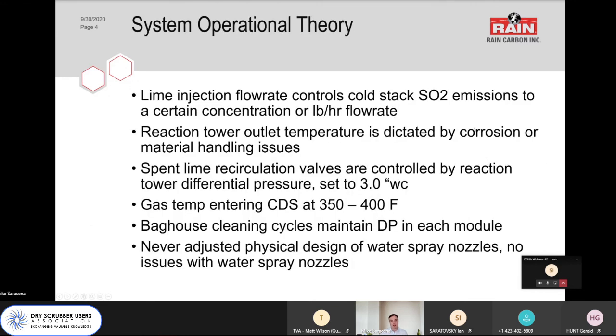System operational theory. So the lime injection flow rate controls cold stack SO2 emissions to a certain concentration or pound per hour flow rate depending on the facility. So that's the direct feedback loop. The reaction tower outlet temperature, which is controlled by the water injection into the scrubbing tower, is dictated by either the corrosion or any material handling issues that we have depending on our facility. The spent lime recirculation valves control how much lime is recirculated back into the reaction tower, and those are controlled specifically by the reaction tower differential pressure, which we currently have set to 3 inches water column.